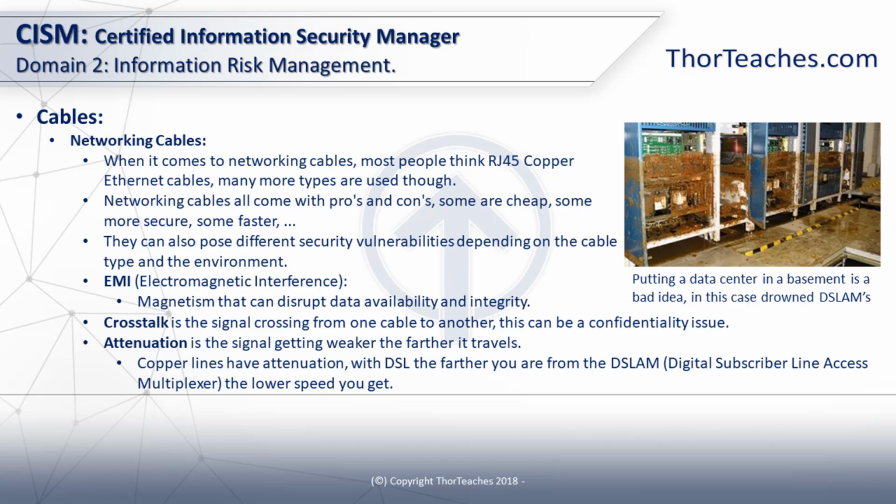Over here on the right, you can see a picture from the ISP I worked at. One spring, Denmark had a tremendous amount of rain, much more than we normally get. There was a lot of flooding, and for some mysterious reason, they had chosen to put that data center with the DSLAM in the basement. You can see in the bottom right corner the tile pulled up from the subflooring, but you can also see the very clear line of how far the dirty water came up on the equipment.